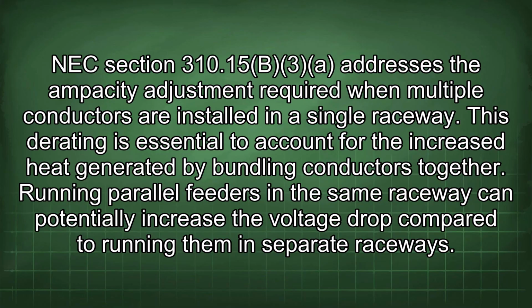NEC Section 310.15(B)(3) addresses the ampacity adjustment required when multiple conductors are installed in a single raceway. This derating is essential to account for the increased heat generated by bundling conductors together.